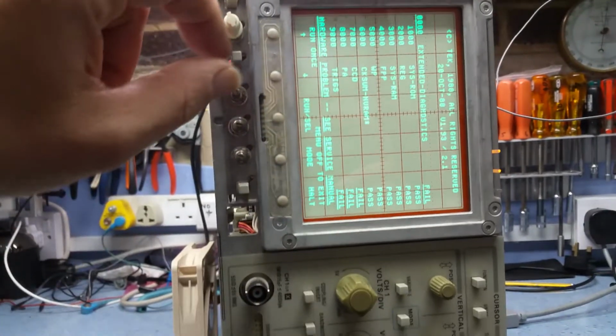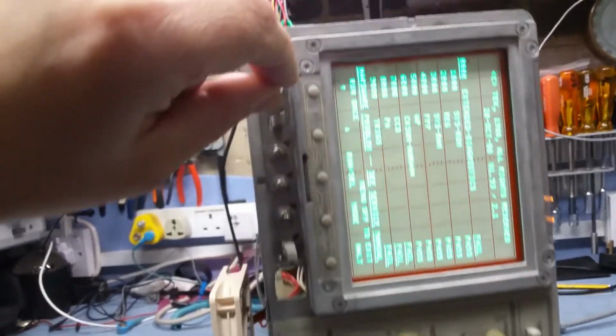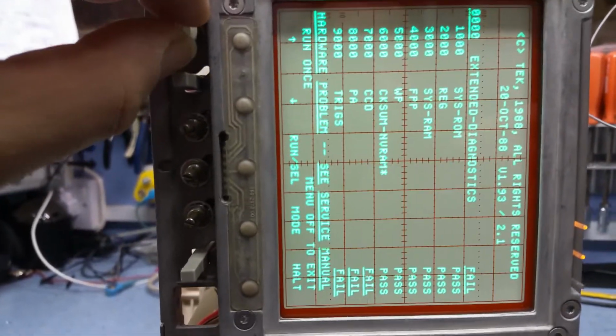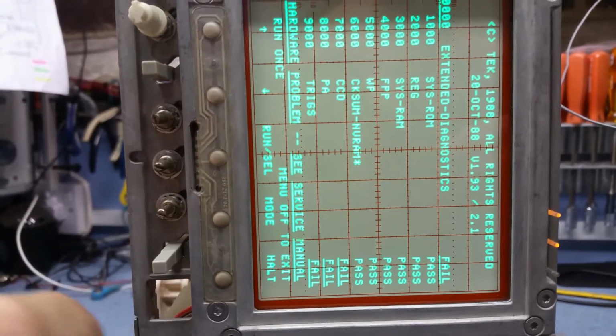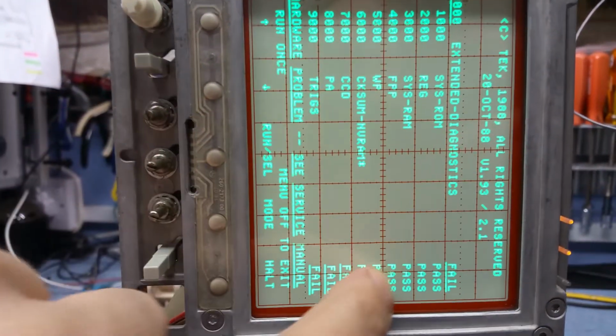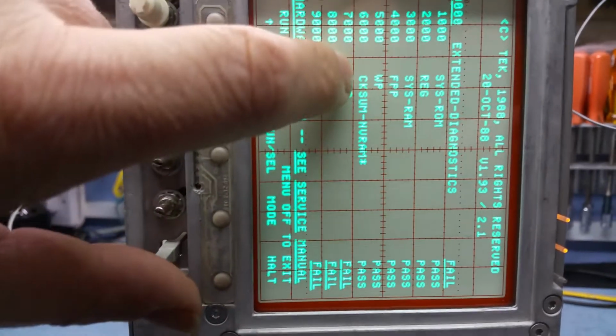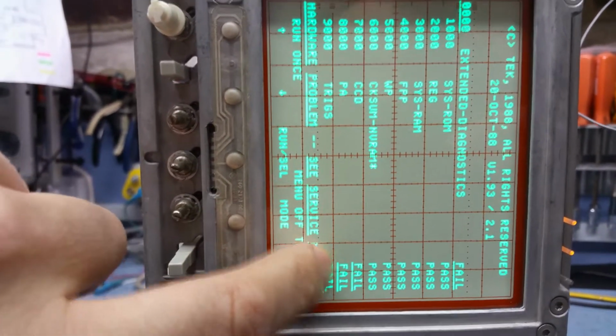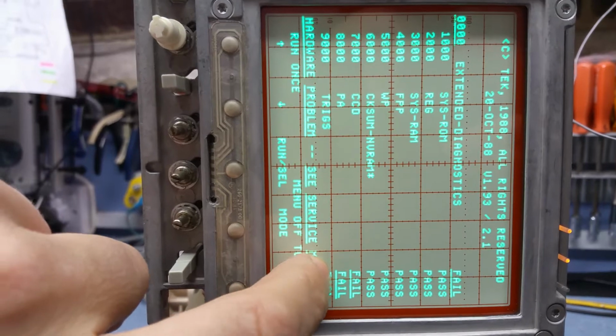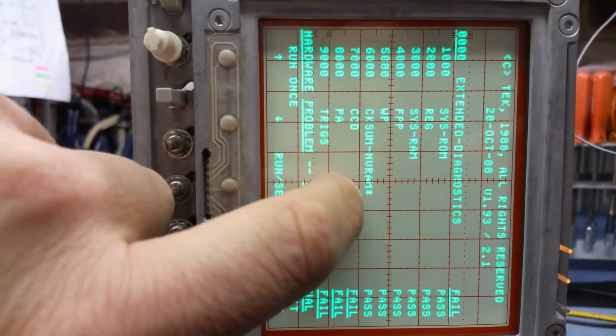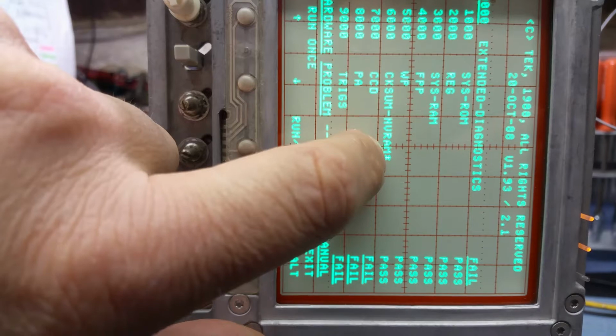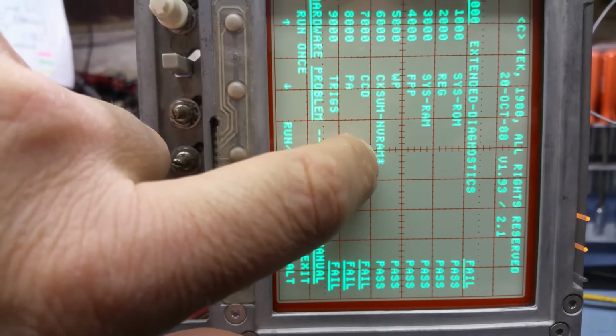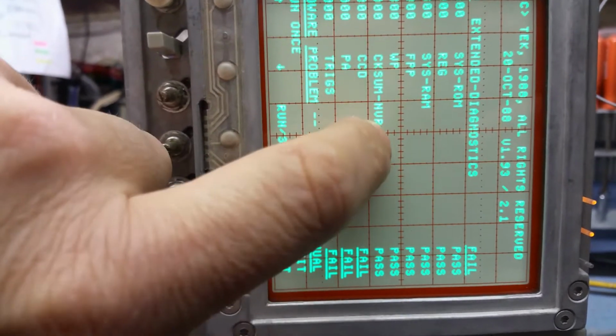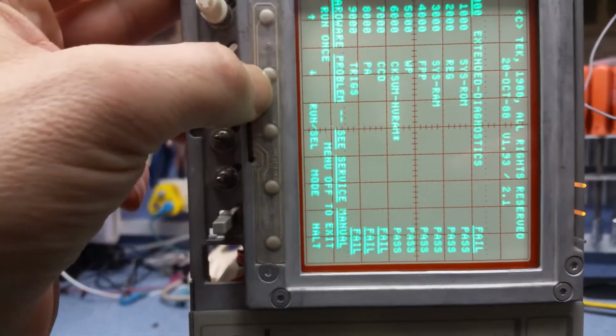You see here, I don't know if you can see how bright this is on the screen. It's difficult to know how bright to put this on the screen because it does sort of wash out. I'm just looking at it now. But you can see here, it's failed extended diagnostics. And the first thing it looks like it fails on is CCD. Now we know this, we've been through all this, and you can get certain parts of it to pass. But you can see here, and I've never noticed this before, it says checksum non-volatile RAM. It says pass, but it's got an exclamation mark on it. So I thought, I've never noticed that before. So I'll go down to check that particular part.